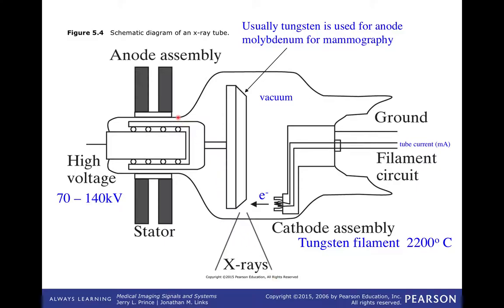This X-ray tube is worth about $25,000–$100,000 — a pretty expensive light bulb. One of the big jumps in CT technology is making these tubes powerful enough to image very fast, since you need a lot of X-rays in a short period of time. These tubes have gone up and up in performance over the last three decades. If you burn it out, it's a big deal. Usually there are things in the system to stop you from imaging too much on a phantom or putting too many X-rays into a person.